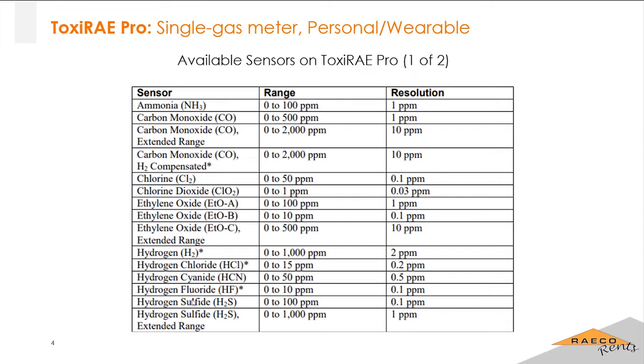You can see there are many, some with different specs. That's another thing to think about when you're doing IH work. What sort of levels of a certain gas, in this case, am I expecting? Or even what resolution do I need? Some people will refer to resolution as accuracy sometimes. So for example, this hydrogen sulfide sensor listed here, 0 to 100 parts per million, can read in increments of 0.1 parts per million. So it's got a little bit more accuracy or resolution.